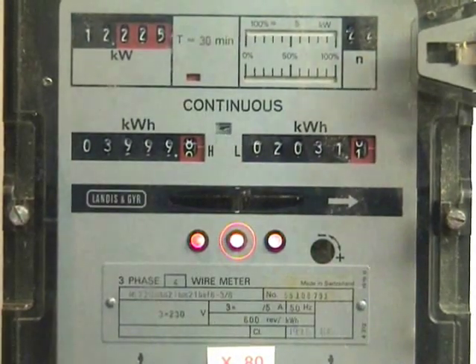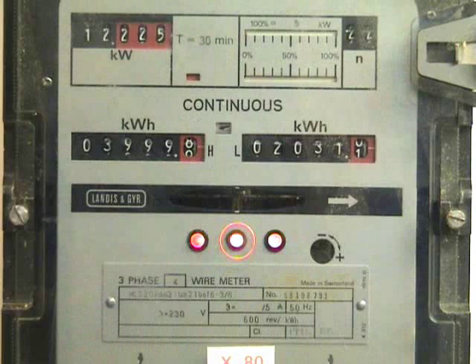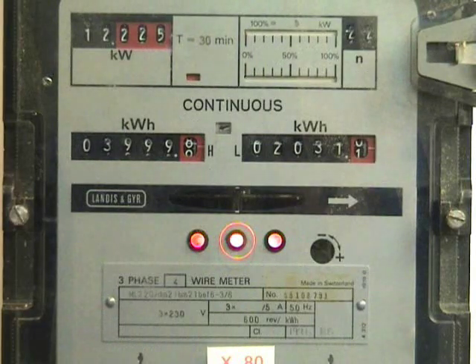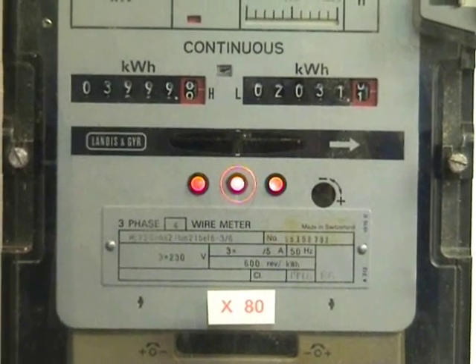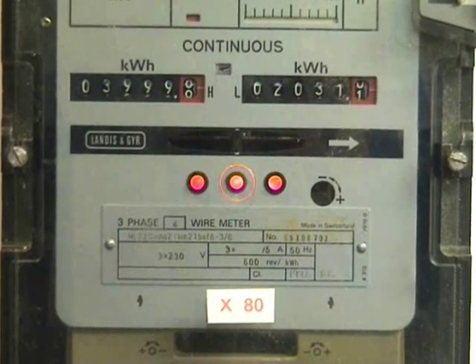The 3 LEDs are potential indicators for the red, yellow, and blue phase. The times-80 multiplier on the meter means the meter was in use on a 400-to-5 ampere CT installation.